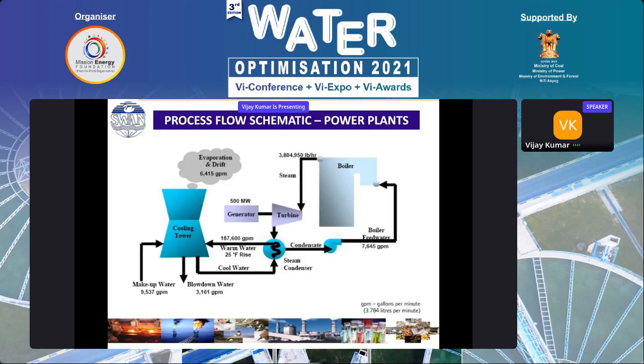But TOC was found to be a hidden problem, and NTPC has done research on it. Now all their chemistry departments are buying a TOC analyzer to periodically check the water quality at different areas. Typically, if you look at a power plant, there are two circuits. One is boiler feed water to the boilers, then the turbine, then the condenser, and then back again like this. And here it is an open circuit.